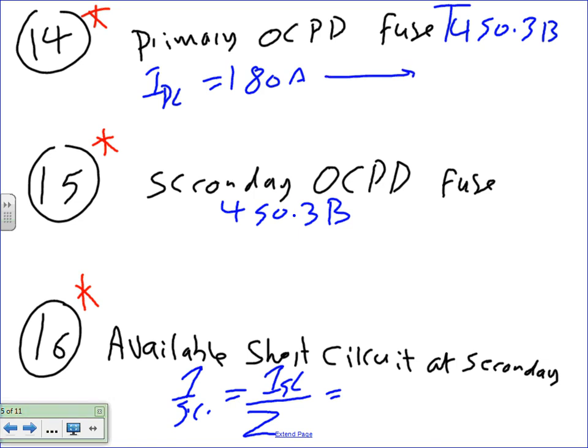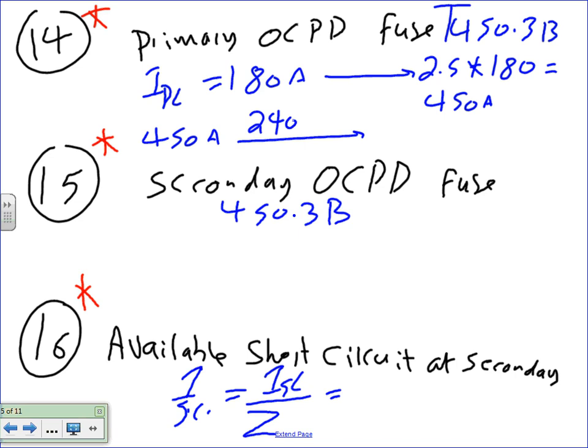So from here, you take 2.5 from the table, you multiply it by 180 amps, and that will give you a healthy 450 amp. Okay, so you take the 450 amp, you need to take it to 240.6. Everybody knows what 240.6 NEC is, right? NEC 2011, 240.6, it will tell you the standard fuse is actually 450. So we hit the jackpot.